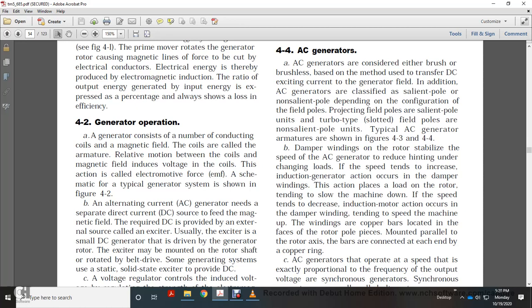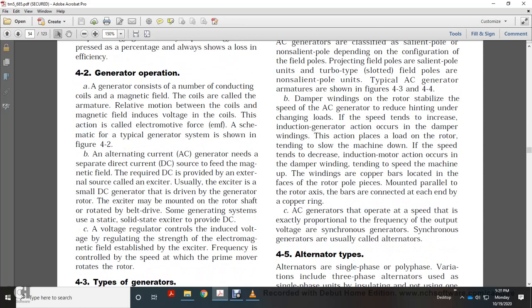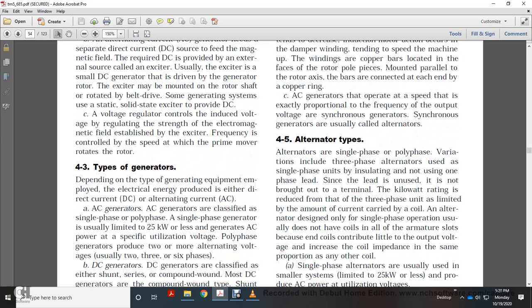When a load is placed on the rotor, tending to slow the machine down, induction motor action occurs in the damper winding, tending to speed the machine up. The windings are copper bars located in the faces of the rotor pole piece, mounted parallel to the rotor axis, and connected at each end to a copper ring. AC generators operate at a speed that is exactly proportional to the frequency of the output voltage. Synchronous generators are also called alternators.